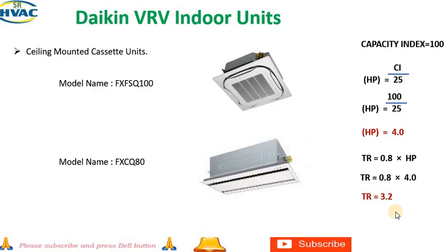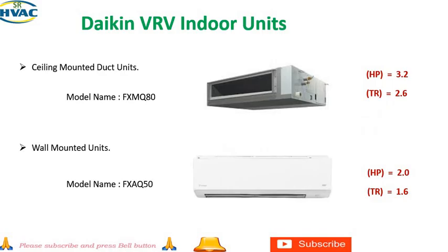Of indoor unit. The next one is model FXCQ80. This is the 2-way cassette unit 80. The TR will be 2.6. You can calculate by dividing by 25 and multiplying by 0.8. You will get 2.6. Okay friends, the next indoor unit we are going to see is the ceiling mounted ductable unit, FXMQ80. Similarly, it will be 3.2 HP. If you divide by 25 and multiply by 0.8, it will be 2.6.